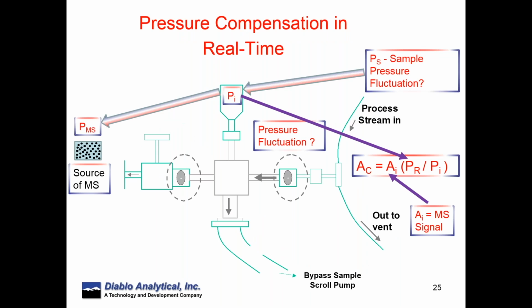So now we have to examine the pressure problem, or potential problem at least. If we, in the upper right, have a process that has some pressure fluctuation, which is often the case, the challenge is that in mass spectrometry, that pressure change for the sample will translate through the interface and will result in a pressure change inside the source of a mass spectrometer. If you have a simple capillary interface, whatever kind of interface you have, this would be the case unless you had instituted some pressure control in your process stream. And sometimes that pressure control can limit the actual sample in terms of how it reaches the analyzer.